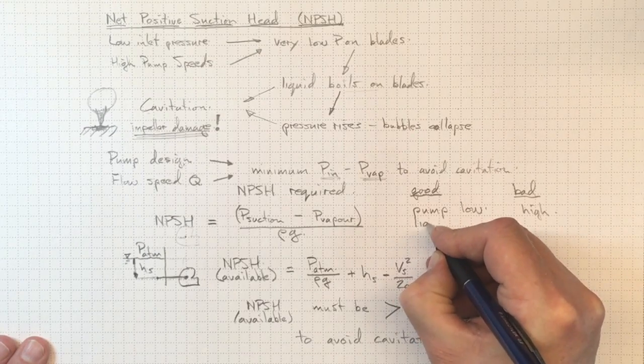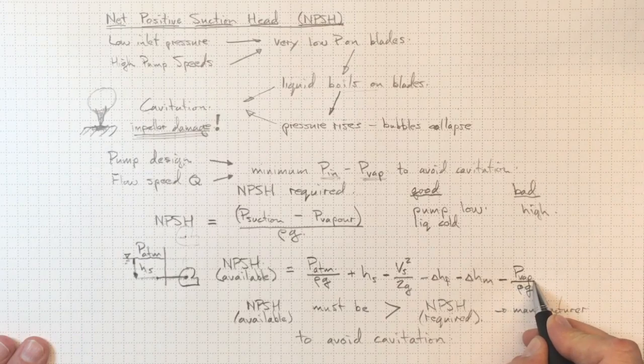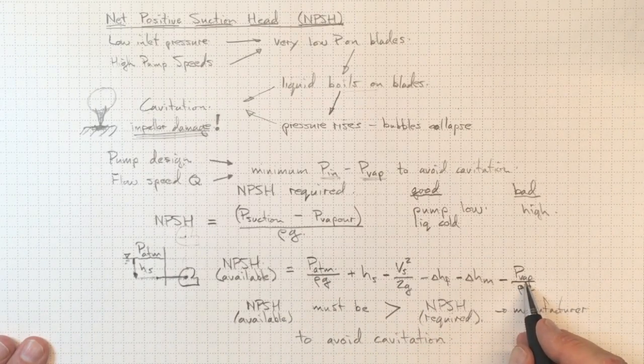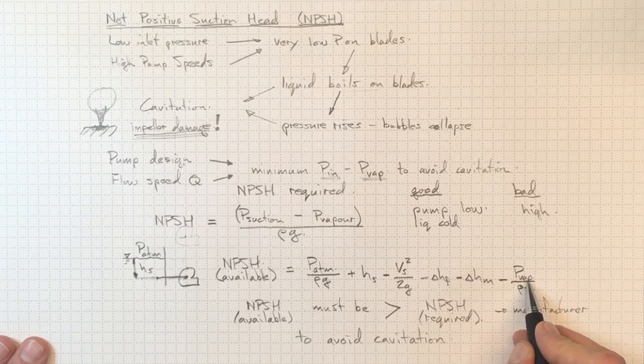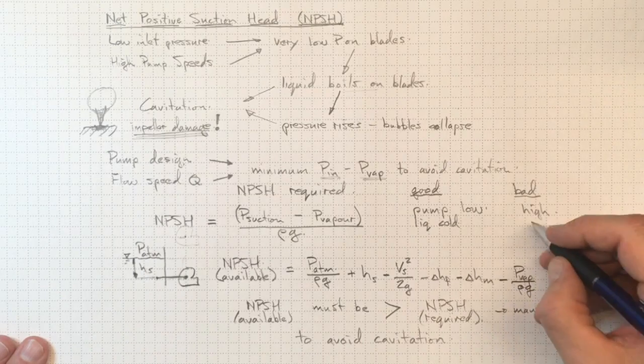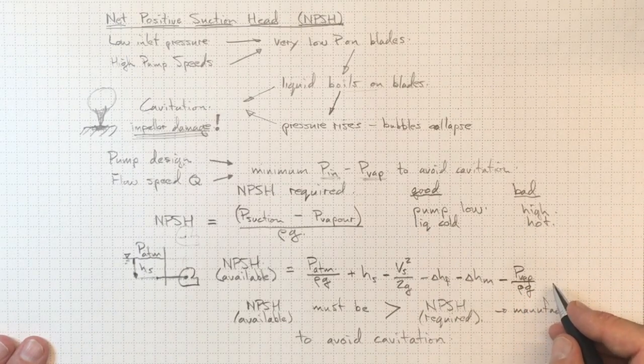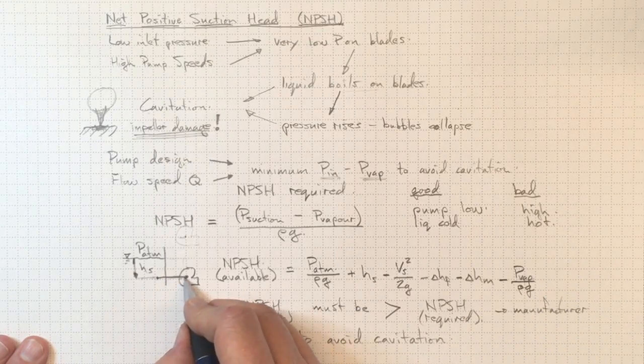Good. If the liquid is cold, then the vapor pressure will be lower and we'll have more NPSH available. So cold fluids, always put your pump on the cold side of the circuit. If there's a heater in the circuit, always make sure you put your pump on the cold side of the heater. On the other hand, if the fluid is hot, that's going to make it more difficult to design your pumping system to avoid cavitation.